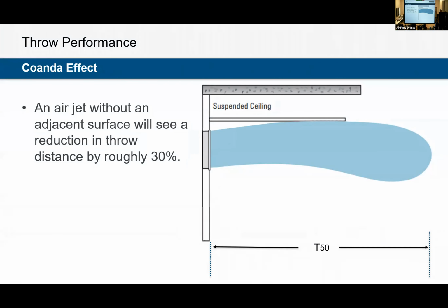All right, I told you we'd come back to throw. Coanda effect. It's a really fun word for a pretty simple topic. Coanda is, I'm going to get the actual definition wrong, but it's the phenomenon that a liquid or gas is going to stick to a surface as long as it can. So when we're talking about ceiling diffusers, we looked at all those smoke videos. The smoke comes out of the diffuser and runs along the ceiling for a set amount of time before it releases and starts dropping into the space. We want Coanda, especially in ceiling diffusers. We want our air to travel across the ceiling before it drops. It keeps us from having draft points in our space.